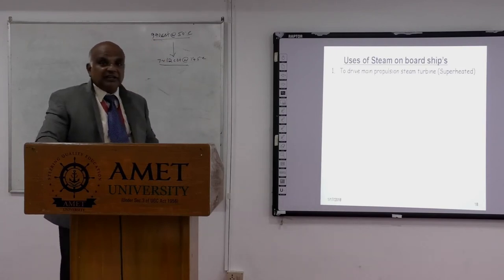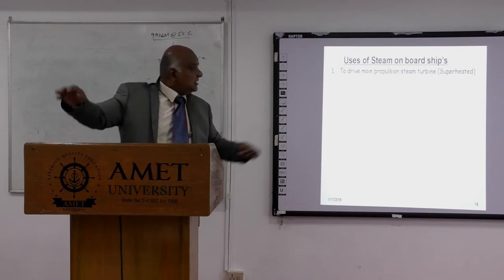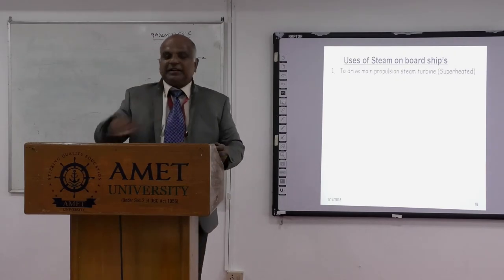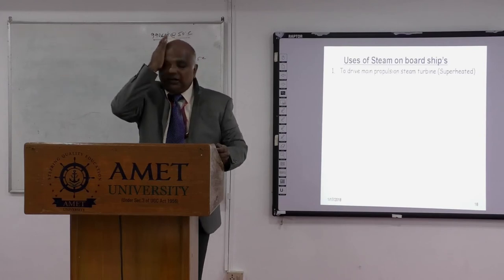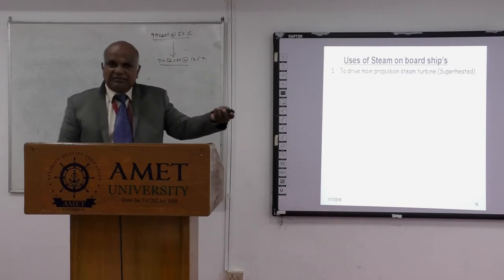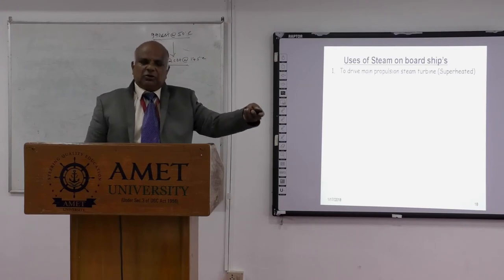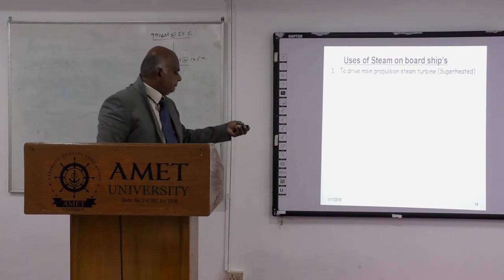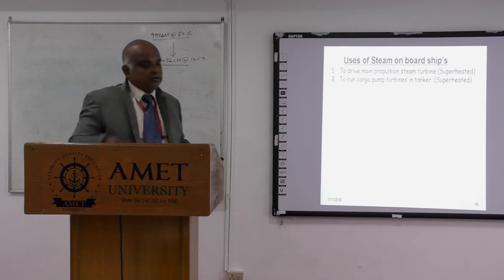There are 14 uses of steam on a ship. First, to drive the main propulsion steam turbine in a steamship, superheated steam is required at around 435 degrees centigrade. Steam exists in three varieties: wet steam, dry steam, and superheated steam. In a motor ship, steam temperatures are around 150 to 200 degrees centigrade and superheated steam is not used as much.